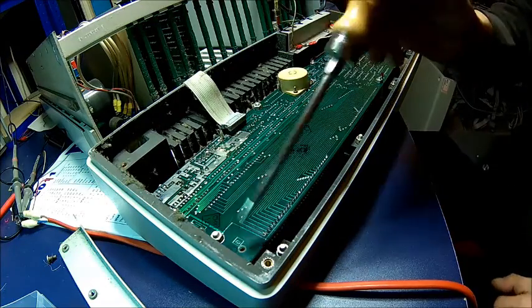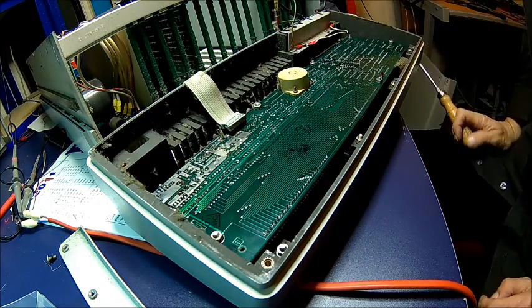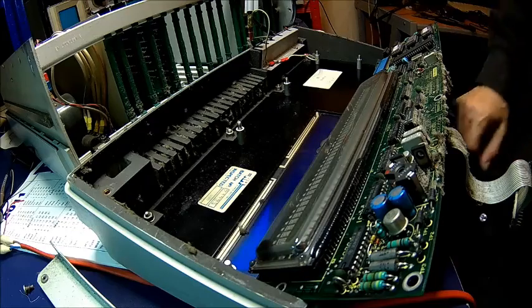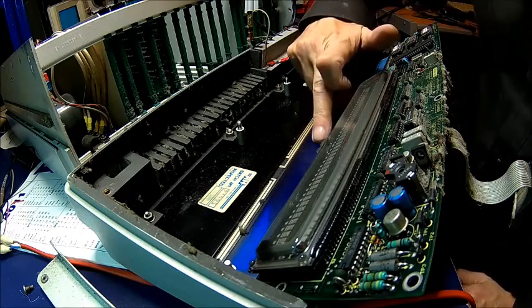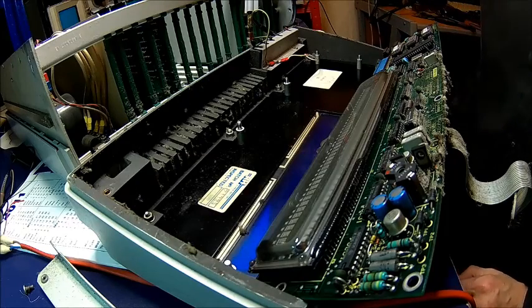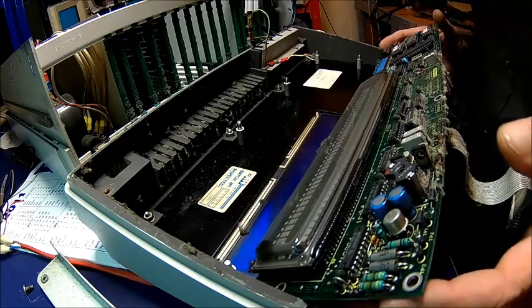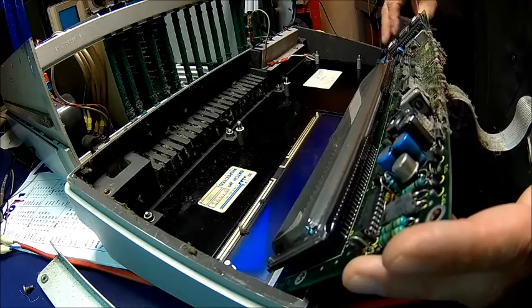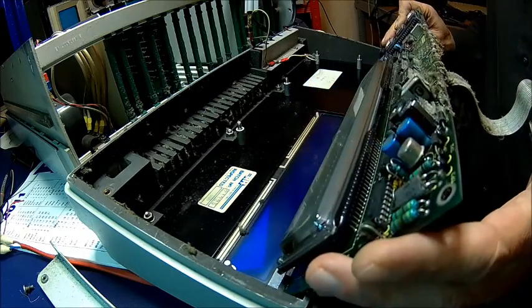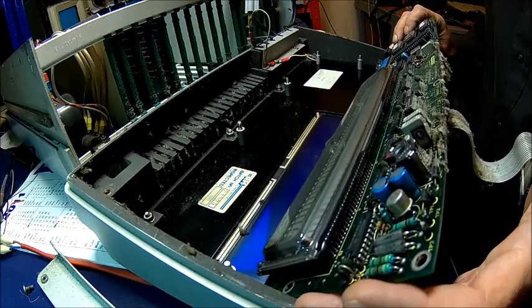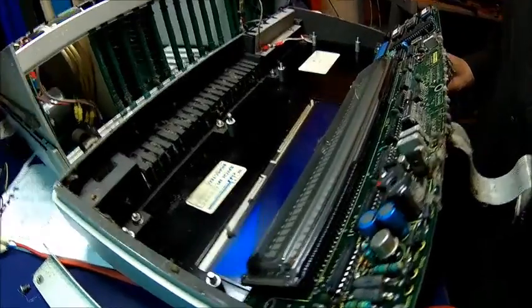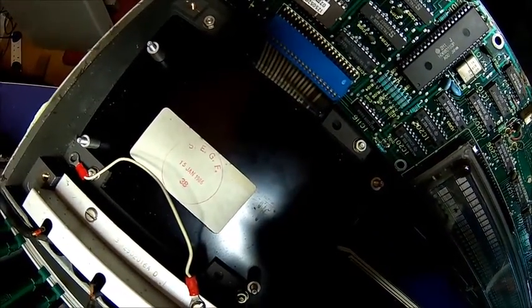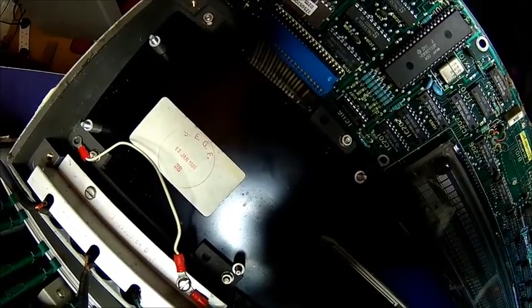Okay, it's just getting those nuts off and I think that gives us access to the front screen so we can clean that a little bit. As expected, it's quite dirty here. I think it's just a matter of cleaning it. With these older units from Solartron you've got to be very careful with this flat ribbon type cable work to the keyboards because they are a bit fragile. And as we can see there is plenty of dirt here. And we found a nice sticker. I don't know if that's visible, but it tells us the unit is manufactured or inspected 15th of January 86.